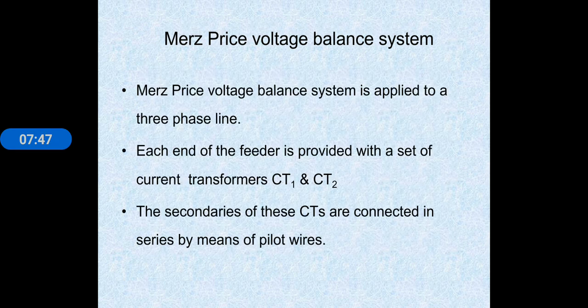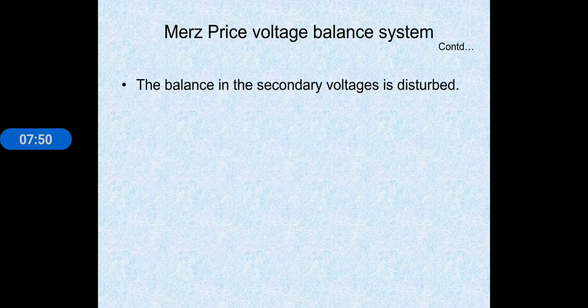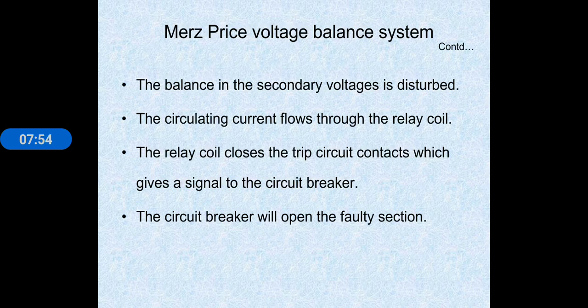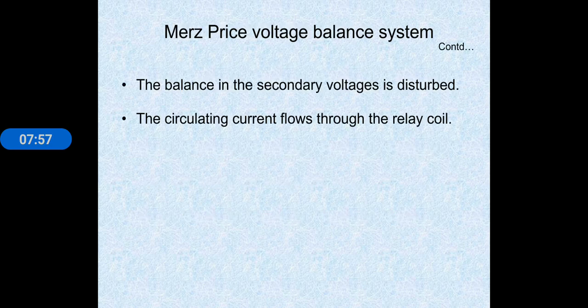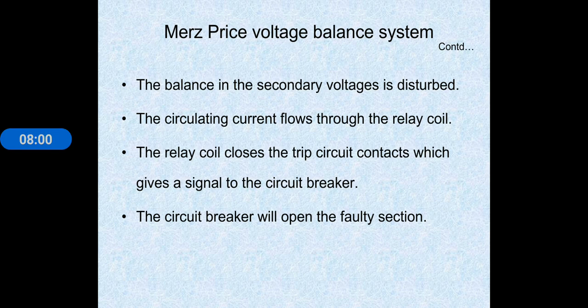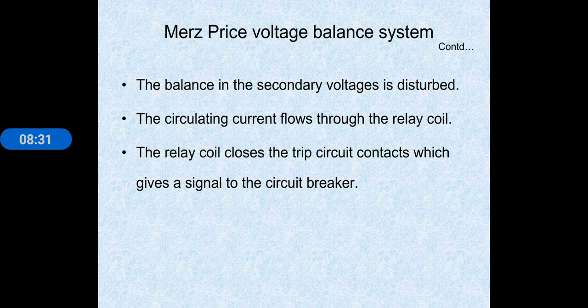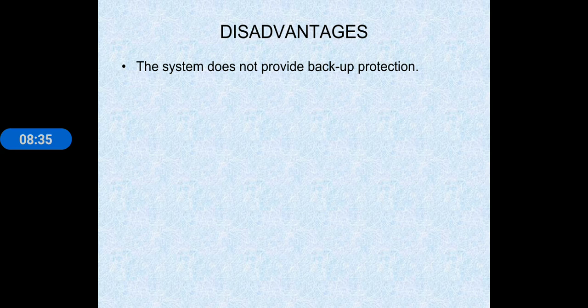Coming to the advantages. This type of system can be used for ring main as well as parallel feeders. This system also provides instantaneous protection for ground faults. Coming to the disadvantages: the system does not provide backup protection.